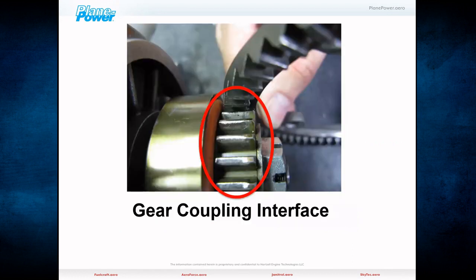Now, gear couplings. If you have a firm old engine and you're doing gear couplings, putting alternators on, you have to be really careful, because the alternator is made by one manufacturer and the base gear I'm holding is made by Continental, while the gear coupling circled here is made by somebody else. So you've got all these plus and minus tolerances, and when all the pluses add up, that's not a good thing.